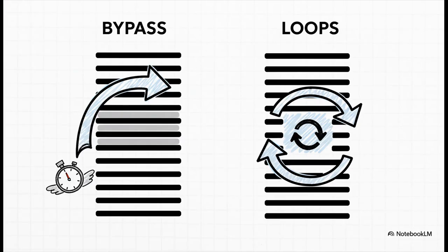On the one hand, this is a powerful tool, no doubt. Let's say you need to bypass a whole section of code for a piece of equipment that's down for maintenance. A JMP can do that. Boom, saves your precious scan time. You can even get clever and jump backward to a label that came before it, creating a loop that forces a chunk of code to run over and over in just one scan.